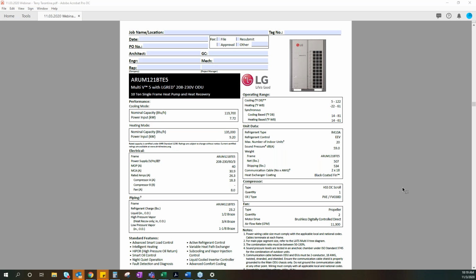A couple things I do want to point out here. This is a 10-ton system. If you look in the electrical box to the left, you see that the maximum overcurrent protection is only 40 amps. This is less than a typical residential 5-ton standard efficiency system. Very, very low energy usage for a 10-ton system.